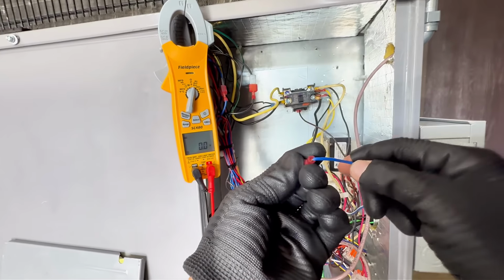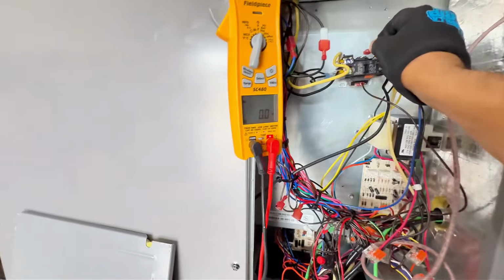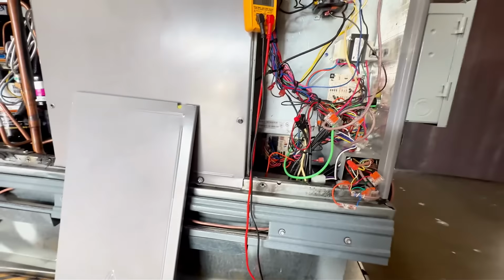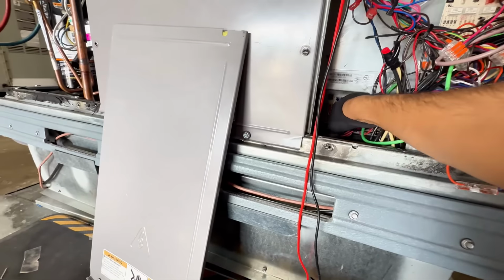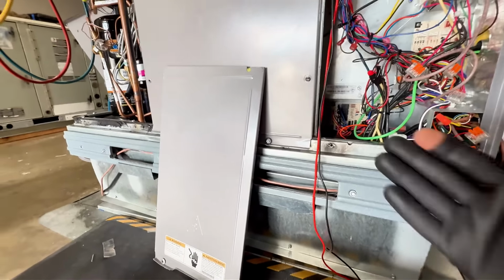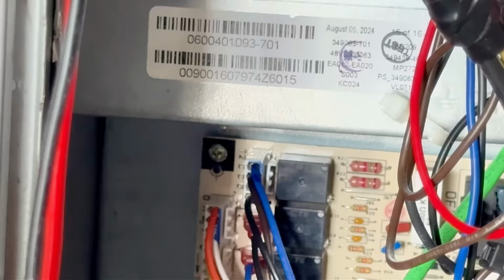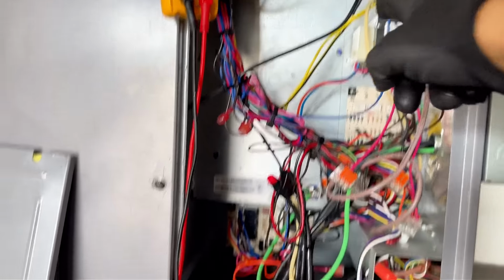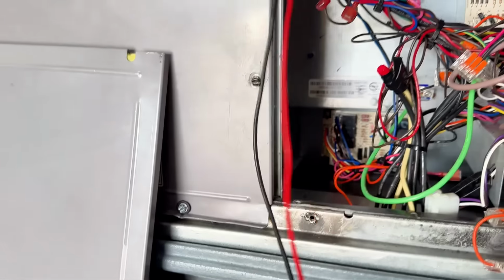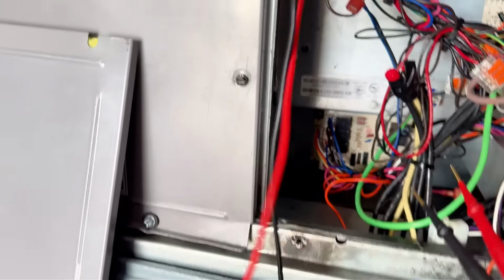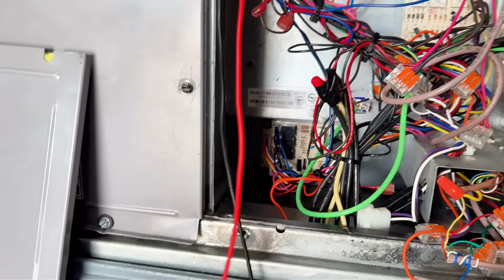So obviously there's nothing wrong with the wire, but I think the problem's gonna be down here. So what I could do too, if you look right there, T2, let me see without putting my finger there so you guys can see. You see right there it says T2? That's the T2, that's the 24 volts going to my contactor coil. So I could check if 24 volts is coming out from that pin, and oh, it turned on.